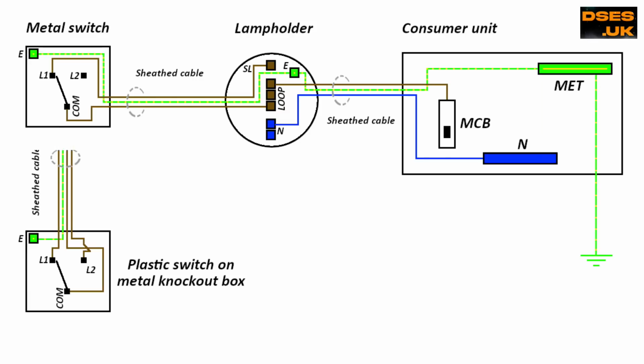Let's bring in switch 2, again not the same configuration as James had, but it'll behave in the same way. Switch 2 also has a circuit protective conductor, and as before, this runs within a cable between other switching cores, one of which is permanently energised. However, this protective conductor is not connected back to the main earthing terminal because it has been cut off by some dickhead kitchen fitter, DIYer, or electrical engineer. As this CPC is in proximity with a live energised conductor throughout the length of the cable, albeit electrically separated by that live conductor's insulation, it is nonetheless capacitively coupled to that conductor because the electric field radiating from it induces a voltage onto our disconnected CPC.